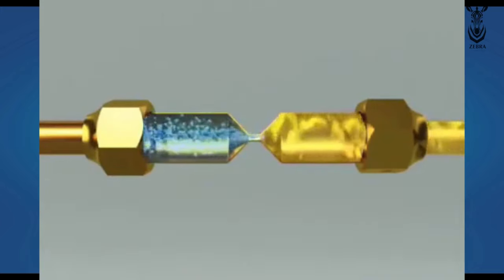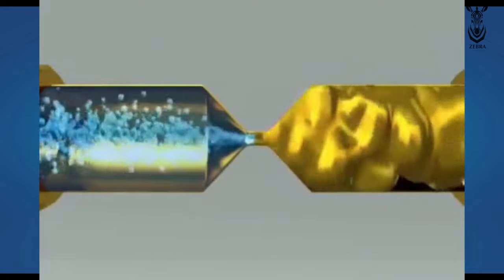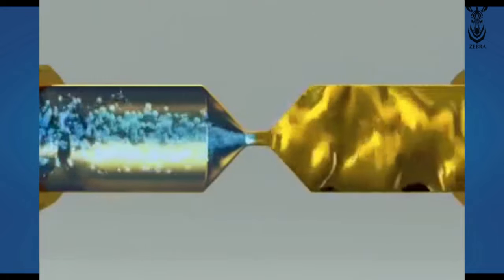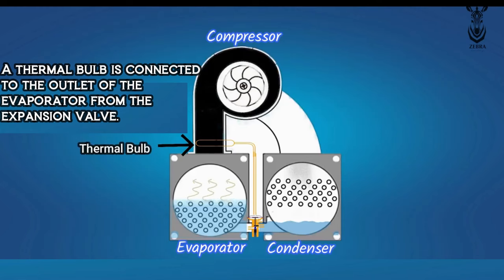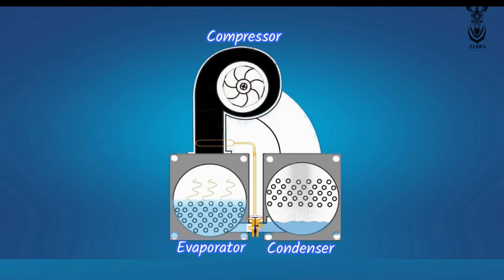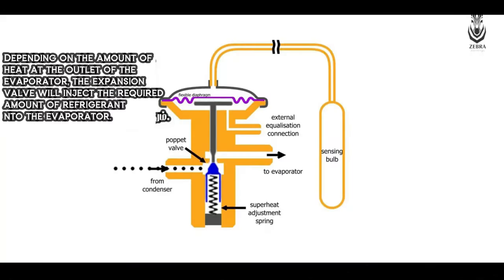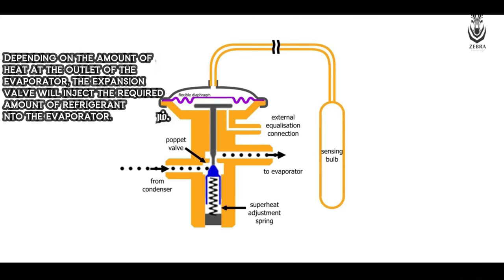The second role of the expansion valve is to send the required amount of refrigerant to the evaporator. A thermal bulb from the expansion valve is connected to the outlet of the evaporator. With the help of this thermal bulb, the expansion valve sends the required amount of refrigerant to the evaporator depending on the temperature of the evaporator outlet.